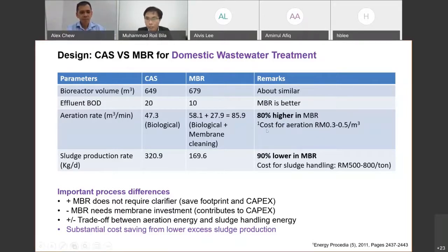Okay, you see here I provide you with the link. This link will give us some of the basic calculation of the cost of aeration. It costs about 30 to 50 cents per cubic meter. Of course, it depends on a lot of factors, but if you go for high capacity, it is this one. Okay, the most striking point and the plus point of MBR is when we consider the sludge production.